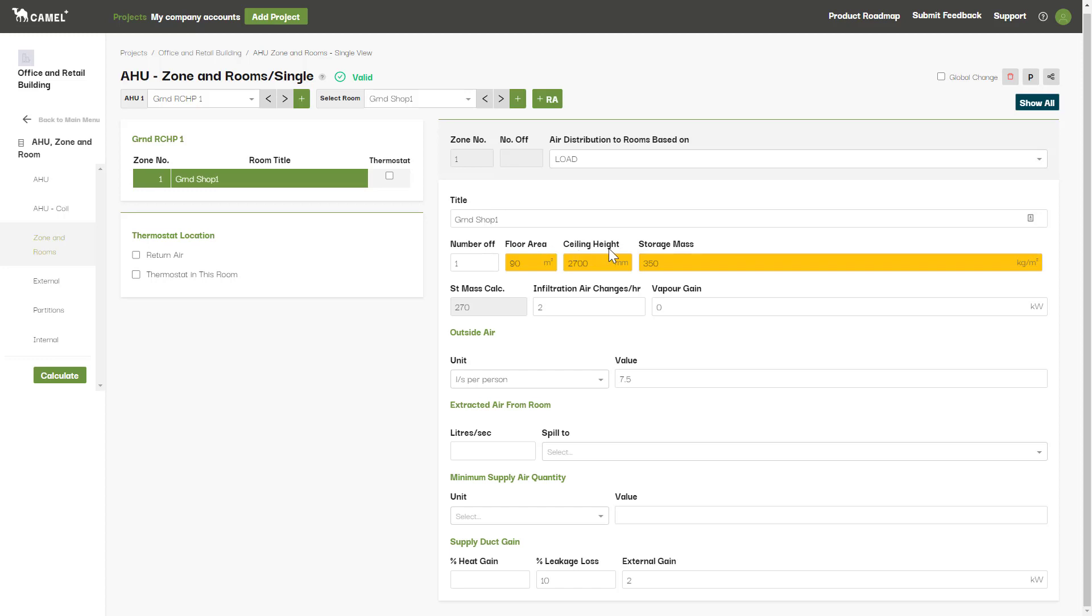Note that the ceiling height entered here is only used to calculate the volume of the room for the purposes of air change rates. If you have a room with a very high ceiling, you may choose not to enter in your actual ceiling height here, and instead just enter in the height that you wish to consider for air conditioning purposes.